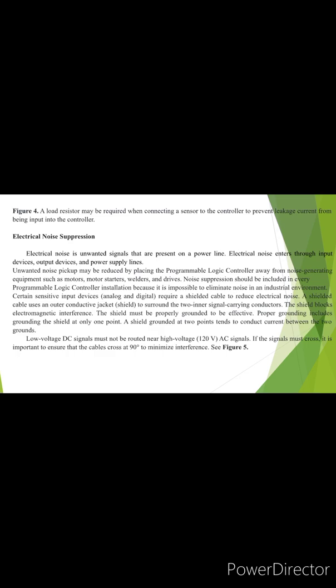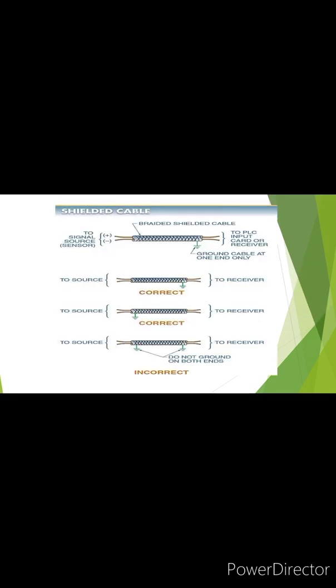Low voltage direct current signals must not be routed near high voltage 120 volts alternating current signals. If the signals must cross, it is important to ensure that the cables cross at 90 degrees to minimize interference. See Figure 5. This is Figure 5, shielded cable. Braided shielded cable to signal source sensor to PLC input card or receiver. Ground cable at one end only. Incorrect. Do not ground on both ends.